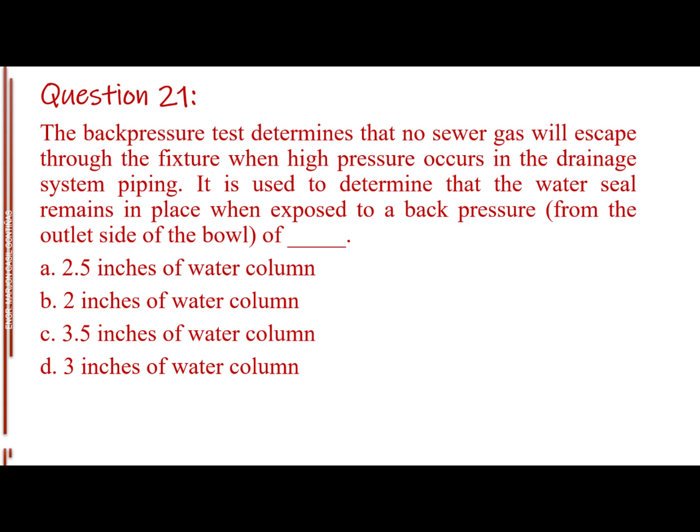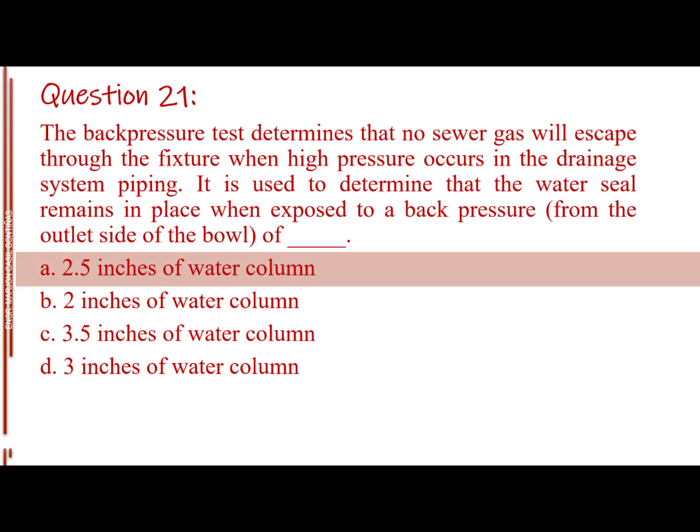Question number 21. The back pressure test determines that no sewer gas will escape through the fixture when high pressure occurs in the drainage system piping. It is used to determine that the water seal remains in place when exposed to a back pressure from the outlet side of the bowl of blank. Letter A, 2.5 inches of water column. Letter B, 2 inches of water column. Letter C, 3.5 inches of water column. Letter D, 3 inches of water column. The answer is Letter A, 2.5 inches of water column.